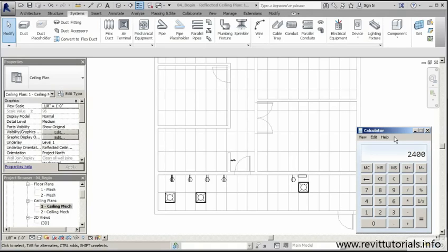And you remember that 180 I showed you, the volt-amps? Now we simply divide this number by that 180. What that lets me know is that that particular strip can handle 180, and any of our receptacles, often known as strips. So we'll type in 180 and divide that. That lets me know that I can place at the most 13 fixtures or electrical outlets throughout this without overloading that particular circuit. Now that's overkill for what we're doing in this kitchen, so we're definitely not going to be getting close to 13. Probably two per wall at the most, so we'll probably be about six, but we definitely know where to go and what not to exceed.